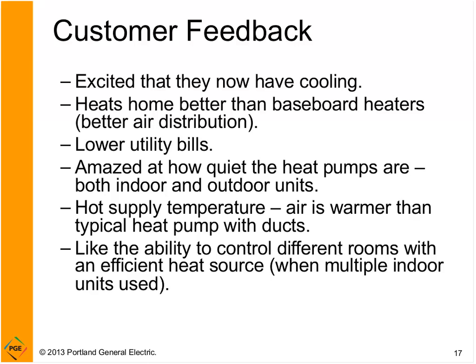And of course, we've covered the efficiency benefits. Lower utility bills are something that customers are always happy to see. They're amazed at how quiet the units are, and that goes for both indoor and outdoor units. Supply air temperature is warmer than a typical heat pump with ducts. With a typical heat pump, there's some temperature loss as the air is distributed through the duct system. In general, ductless heat pumps just provide a hotter supply air temperature. I've taken some temperature readings out of ductless heat pumps, even in, let's say, 40 degree temperature, and I've found supply temperatures between 110 and 120 degrees. So pretty warm air coming out of these units.